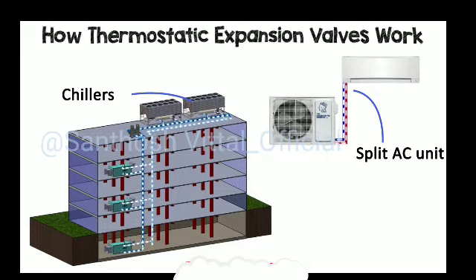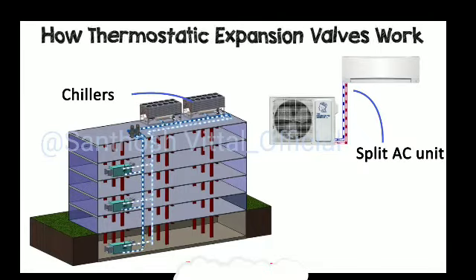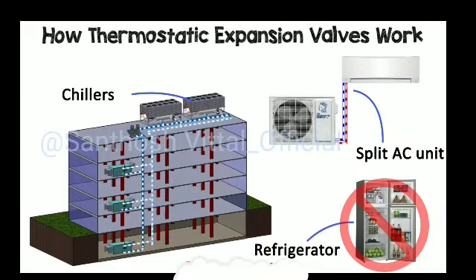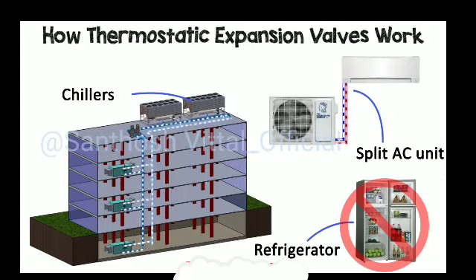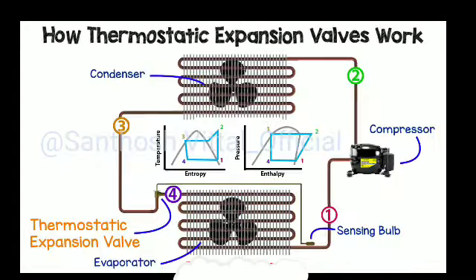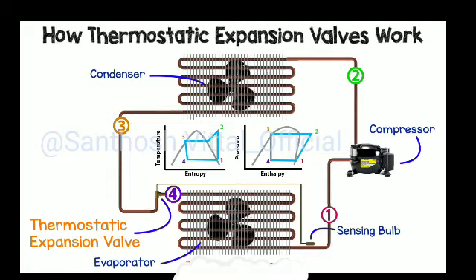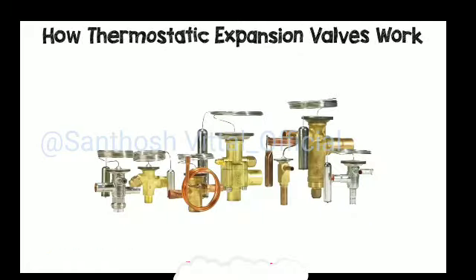Well, the thermostatic expansion valves are used in many refrigeration systems, everything from simple split units all the way up to big chillers. Small refrigeration units, such as household refrigerators, typically wouldn't use a valve. Instead, they would use a fixed orifice capillary, but we'll look at that in another video. Now, it doesn't matter which type of expansion device is used, they can all be found in the same location, which is just before the evaporator. Now, there are a lot of different designs for this valve out there. I've just got some examples on the screen now.